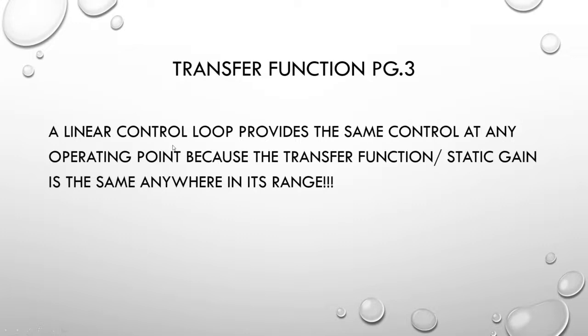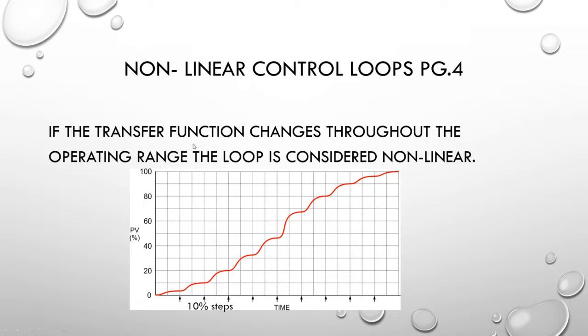A linear control loop will provide the same control at any operating point because the transfer function and the static gain is the same anywhere in its range. When we get into non-linear control loops, this tells us that the transfer function changes throughout the operating range. Using 10% steps, you'll see that one step made about a 4% change, another made about 6%, and another made about 10%. So everywhere along this line, the static gain is different — and that's what we're addressing in this lecture.